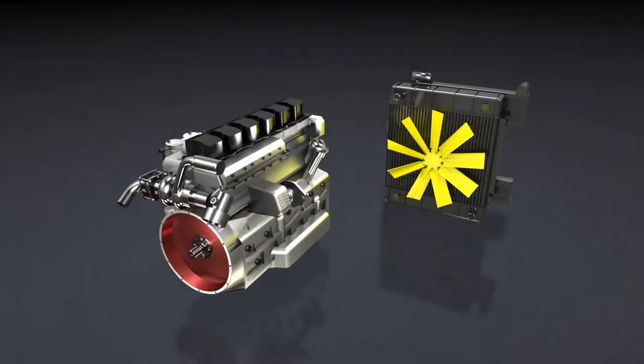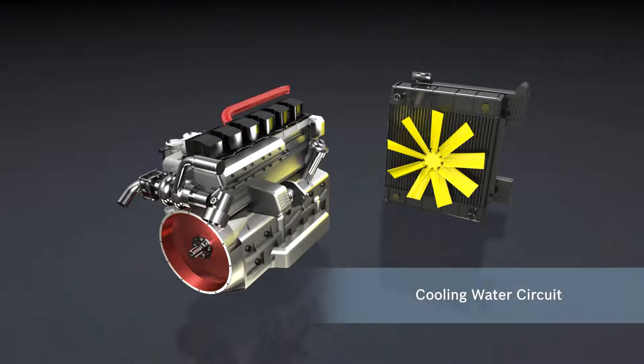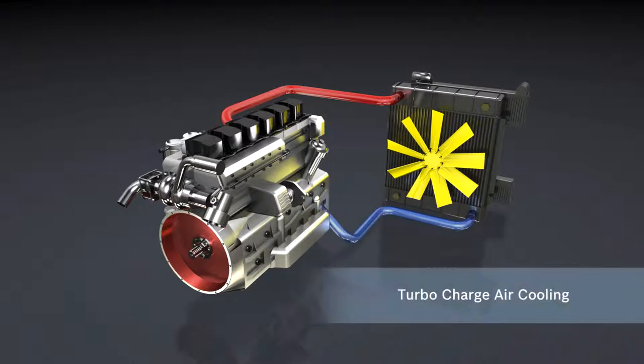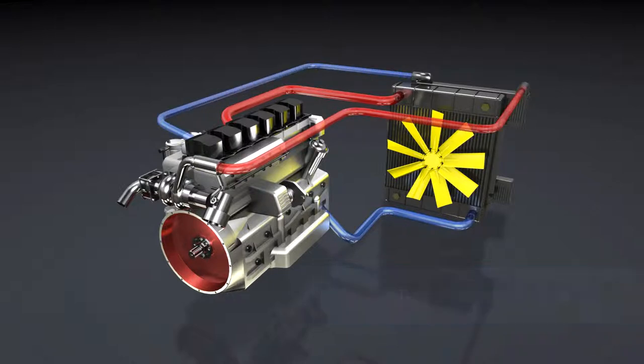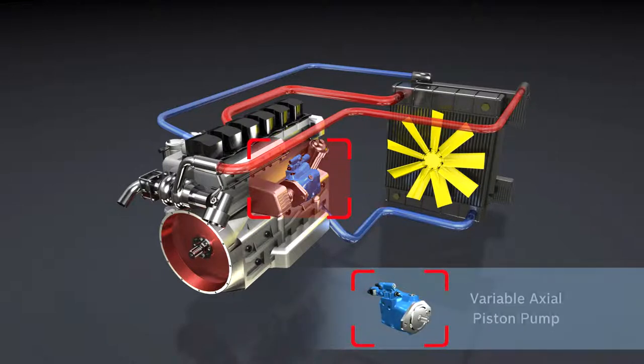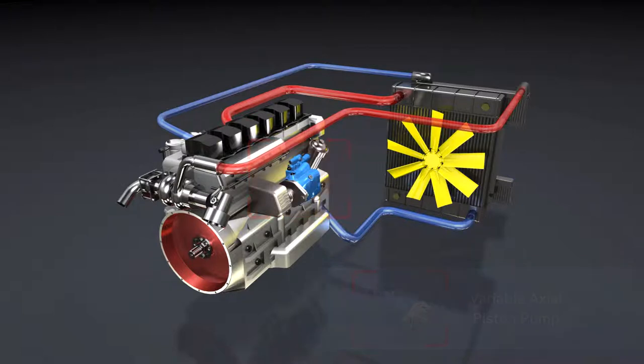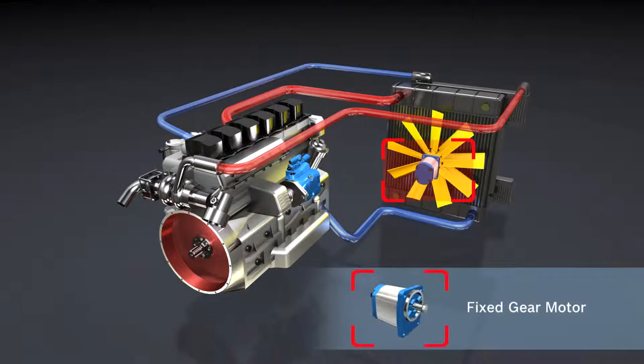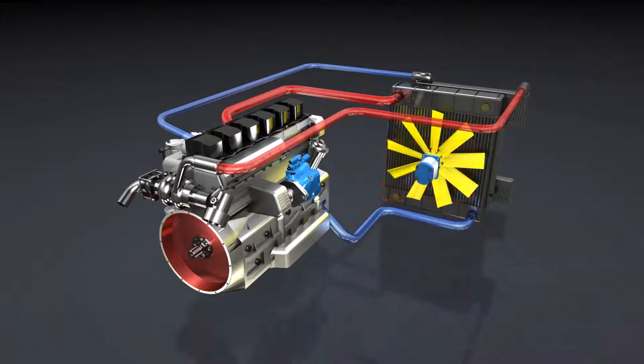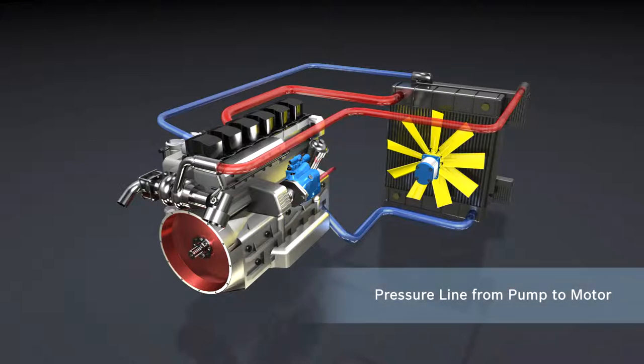A hydrostatic fan drive with a cooling system can be structured as follows: cooling water circuit, turbo charge air cooling, variable axial piston pump, fixed-gear motor, and hydraulic circuit with or without oil cooler as required.